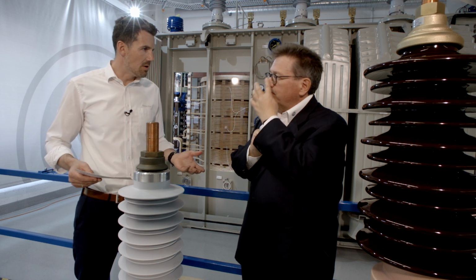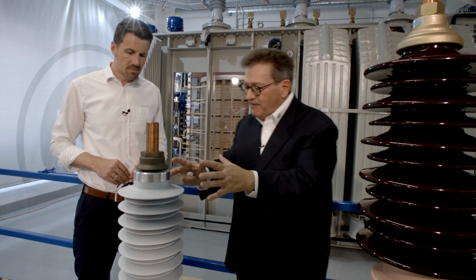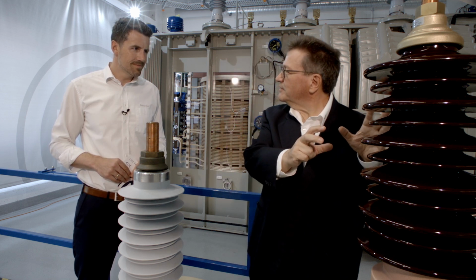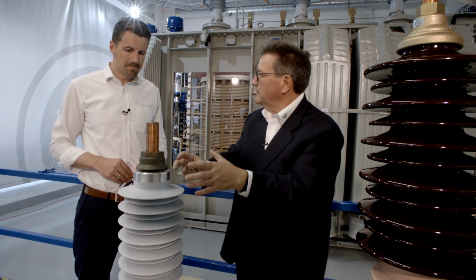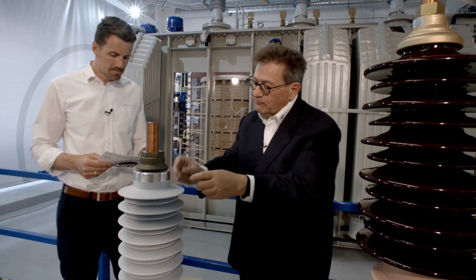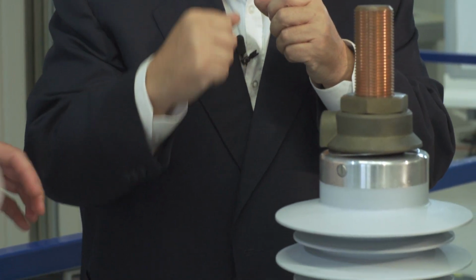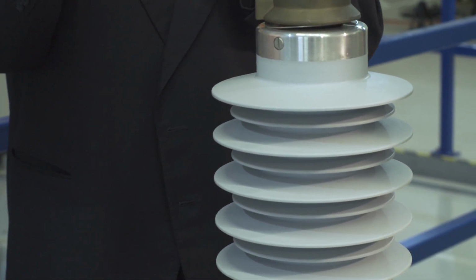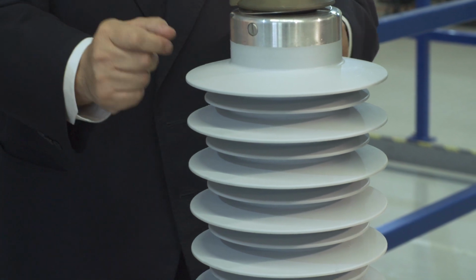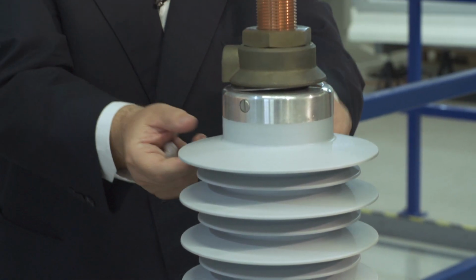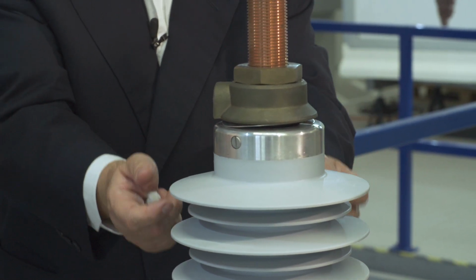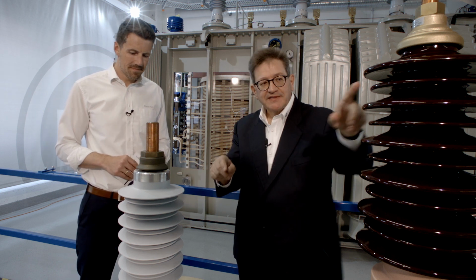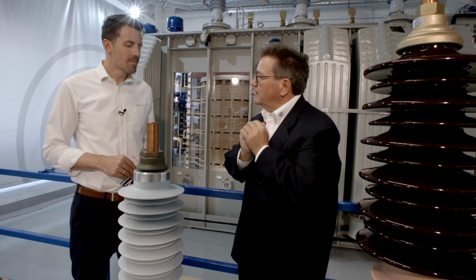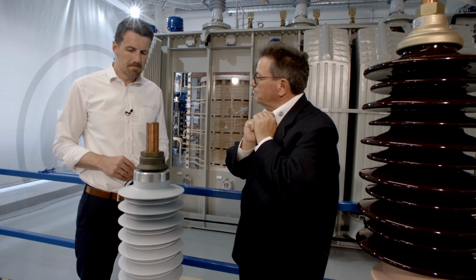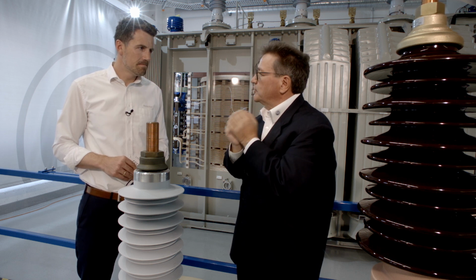Why are polymeric bushings preferable nowadays? Very simple, very easy. We have replaced the weak point of the porcelain insulator bushing, introducing what we call polymeric bushings. Here, the insulation is granted by a combination of a glass fiber tube, which gives much stronger strength as far as bending forces are concerned, and over which we mold a silicone rubber shed form to recreate the same function of the sheds in a porcelain insulator, to have the same creepage distance, and to have the same or even superior electrical features.